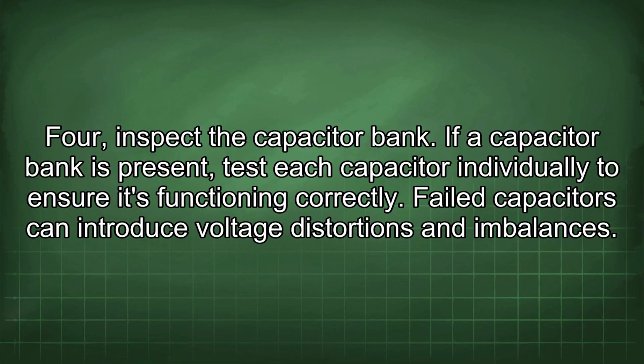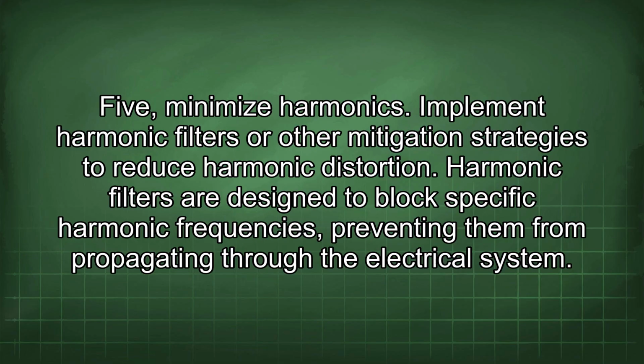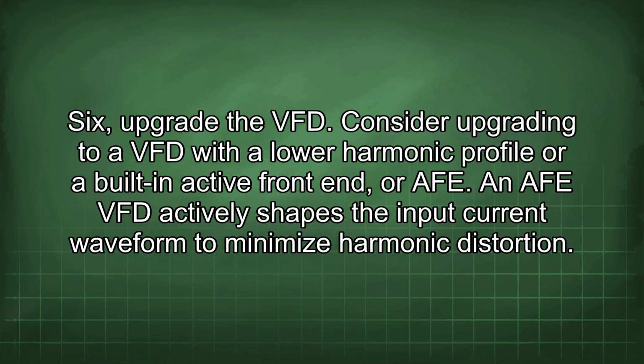4. Inspect the capacitor bank. If a capacitor bank is present, test each capacitor individually to ensure it's functioning correctly. Failed capacitors can introduce voltage distortions and imbalances. 5. Minimize harmonics. Implement harmonic filters or other mitigation strategies to reduce harmonic distortion. Harmonic filters are designed to block specific harmonic frequencies, preventing them from propagating through the electrical system. 6. Upgrade the VFD. Consider upgrading to a VFD with a lower harmonic profile or built-in active front-end, or AFE. An AFE VFD actively shapes the input current waveform to minimize harmonic distortion.